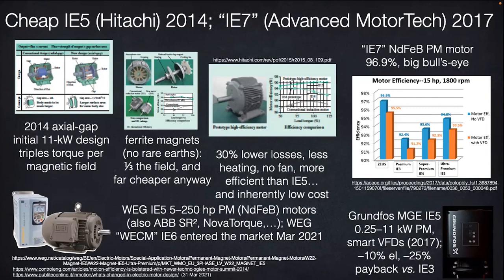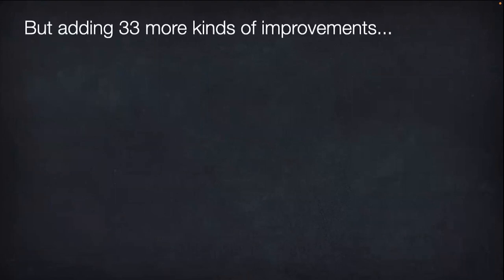But there's a lot more to motor efficiency than the nameplate ratings. The standard two-measure retrofit—upgrading to IE2s and usually adding ASDs—captures only about half the savings available from a whole-system approach to the drive system alone, without improving the pumps and pipes, the fans and ducts, or other downstream equipment, which should, of course, happen first.